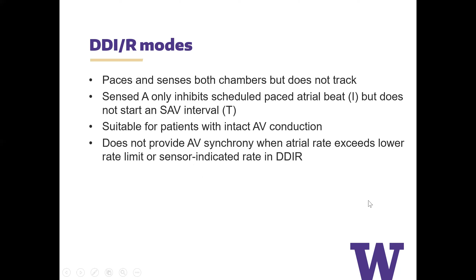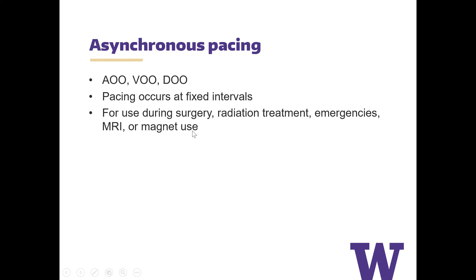And then there are asynchronous modes of pacing, which are AOO, VOO, and DOO. This is pacing that occurs at very fixed intervals, and it's for use during surgery, during radiation treatment, during emergencies, during MRI, or magnets. You can apply a magnet over most pacemakers, and it will go into an asynchronous pacing mode. So that's good to keep in mind in emergency situations.